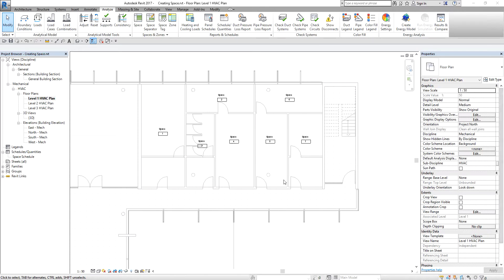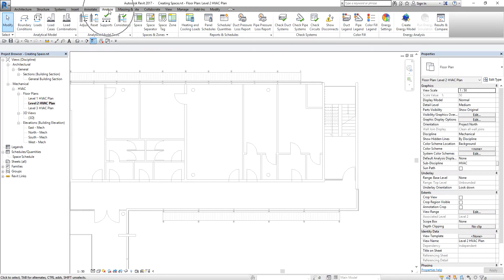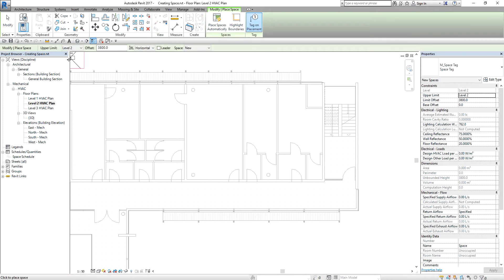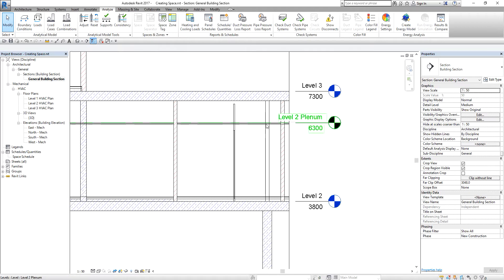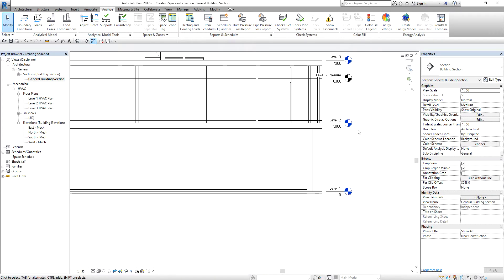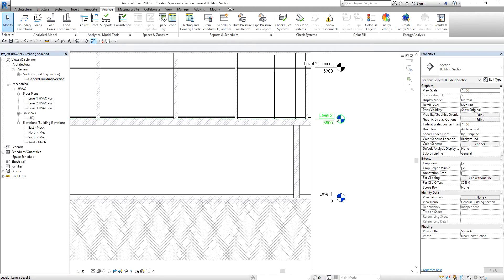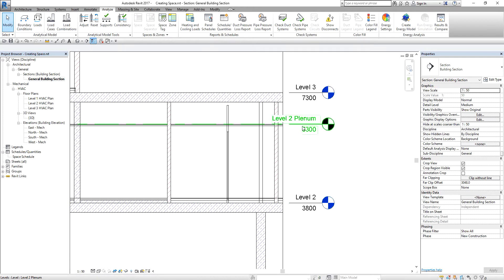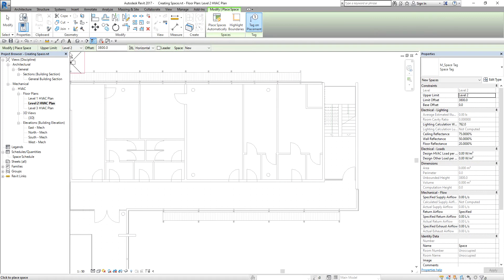Next, I'm going to place spaces on Level 2. I'm going to open the Level 2 HVAC plan and follow the same procedure: Analyze, Space. I'm on Level 2, so I want to create spaces from Level 2 up to Level 2 Plenum. Just to remind you — we need to consider the ceiling, which is why we created that level. So I'm creating spaces from Level 2 to Level 2 Plenum. I select Level 2 Plenum as the upper limit, with an offset of 0.